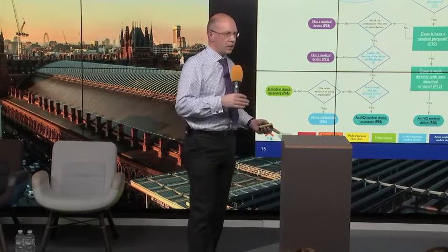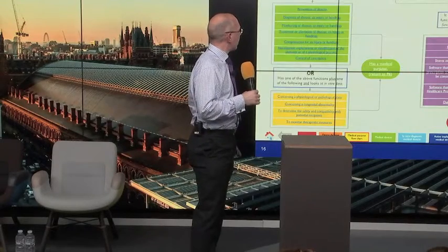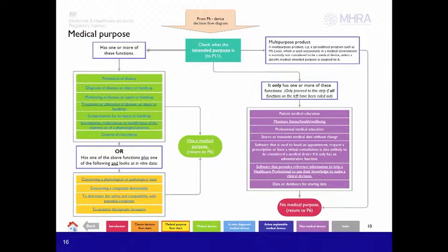So what help can we give? Our guidance, which came out last year, is an interactive document and is aimed at the most common questions we've seen about CE marking. And it just covers standalone software, not software that's part of a device. So we have lots of nice flow diagrams for deciding which route to take of the 3 device directives. We look at what medical purpose there is. So we provide a list of things that we consider not to be devices, and we look again at the functions that I discussed earlier.